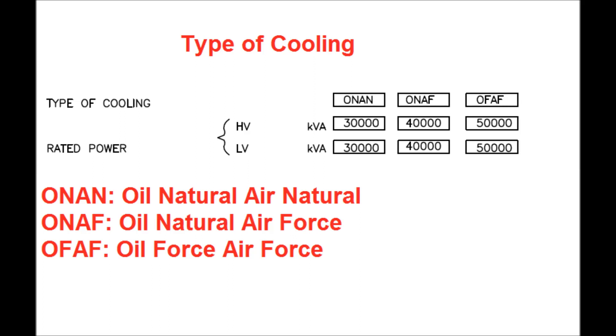Oil natural air forced cooling can be done up to 80% loading of the power transformer, that is up to 40 MVA capacity. Beyond that, the type of cooling that must be implemented is oil forced air forced, that is OFAF, and this must be done up to 100% loading of the power transformer.